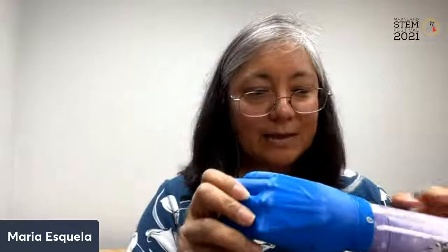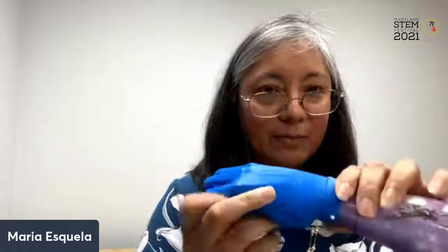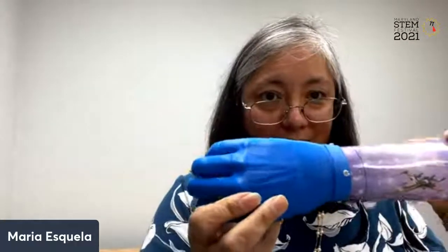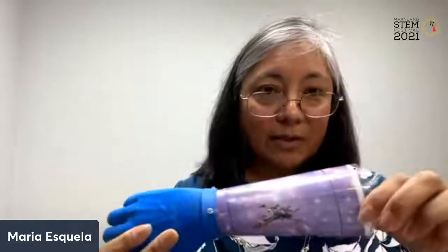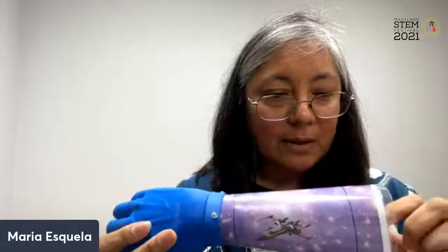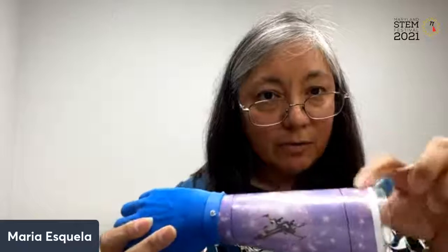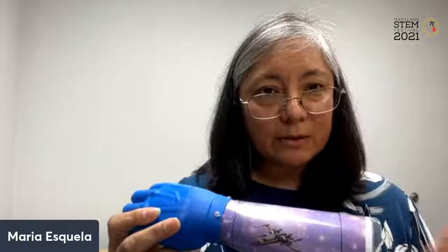This design for an arm was very simple because you could pre-print the hand and the thumb as the only two pieces for the hand. There's a ring here. This is something that could ship flat. It's just laminated paper, but it was strong enough to be a forearm. So the only thing you needed to measure in order to adapt this to the wearer as a custom sized device was just this small ring of filament that would be easy to print quickly, even if you lived in a place where electricity was only available to you for a short period of time.